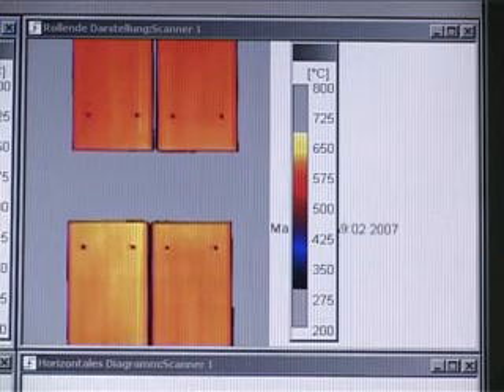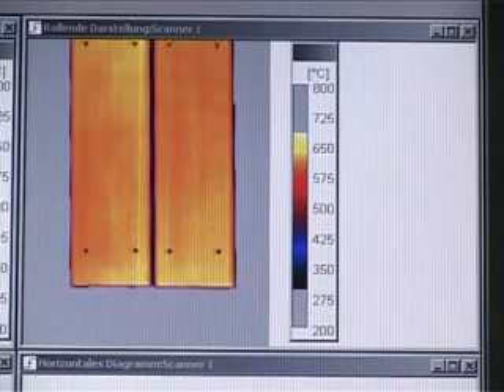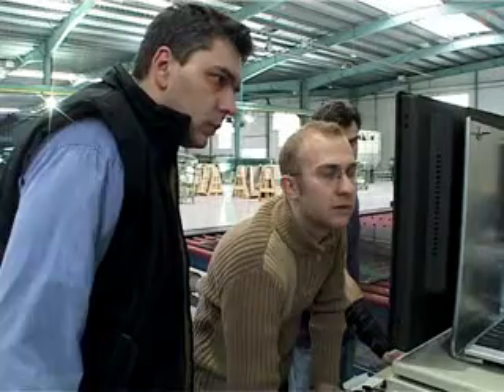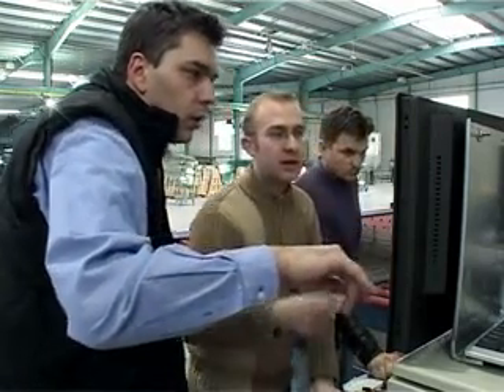The GS 110 software combines all measured data into a two-dimensional thermal image, which is displayed in real time on a computer screen. If temperatures are not within the specified range, an alarm is triggered to allow for corrective actions. The operator can then make the necessary modifications in the furnace settings, either manually or through a fully automated control loop. Raytek is the first infrared sensor manufacturer to offer a system specifically designed to monitor the temperature distribution of low-E glass. The main advantage of the GS 110 system is an automated emissivity correction mode which compensates for very low or unknown emissivity values.